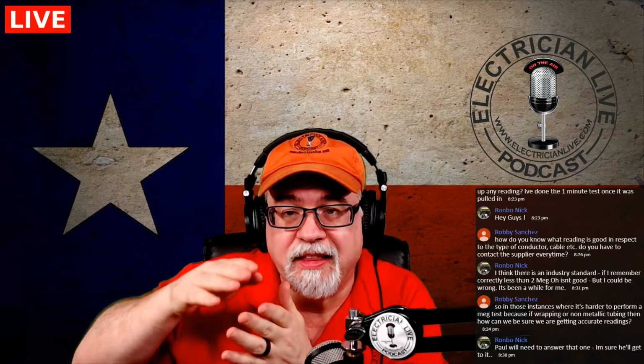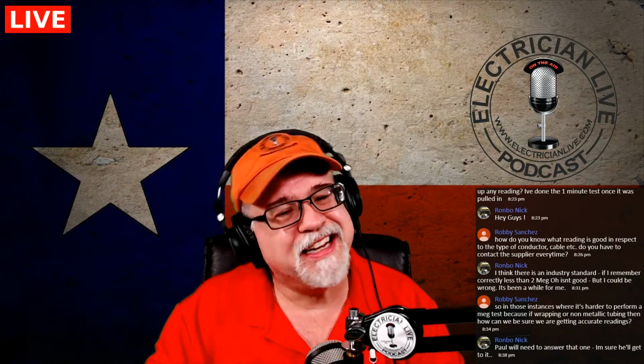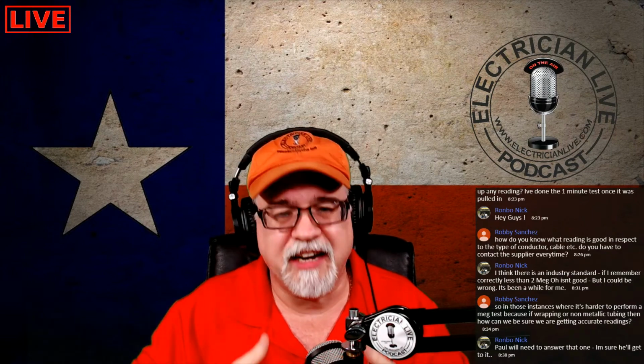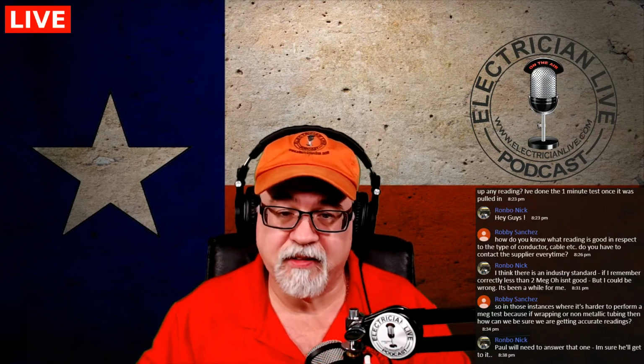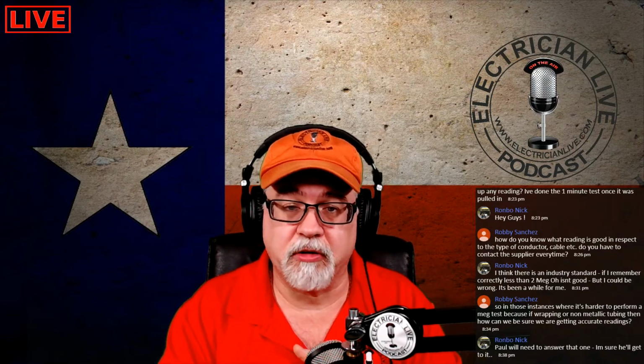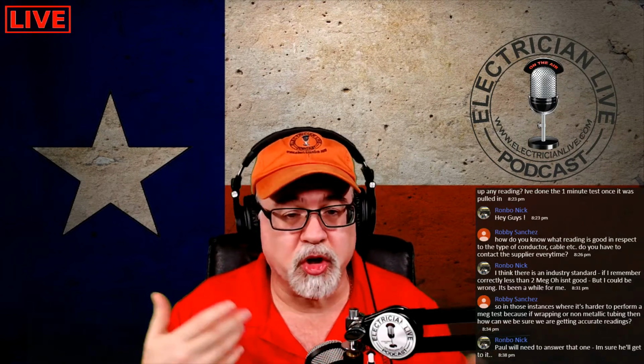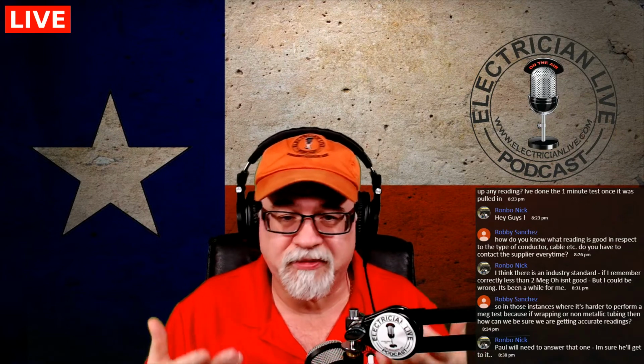And it will tell you how much absorbs to it because there's two paths that are mutual, okay? They're mutual. They're in the same cable. So the chances of getting a reading that's acceptable is good. Perfect for medium voltage. Perfect for high voltage that gives you that return path. But individual insulated conductors, it's very hard to do. If it's in a metal raceway, you just increase your chances. If it's all PVC and everything's insulated, you're going with numbers just to make you feel warm and fuzzy.